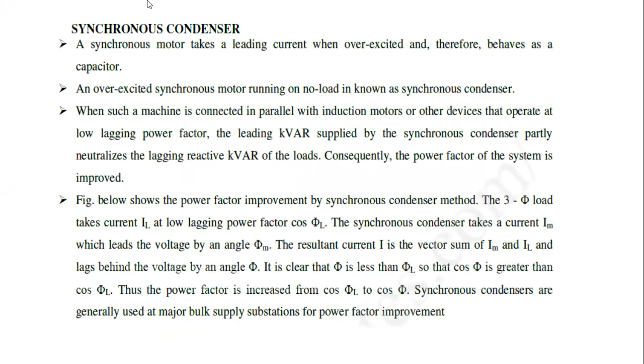Therefore, the resultant current I is the vector sum of IM and IL and lags behind the voltage by an angle of phi. It is clear that phi is less than phi L, so cos phi is greater than cos phi L. Therefore, the power factor increases from cos phi L to cos phi. The synchronous condensers are generally used at the major bulk supply stations for power factor improvement.